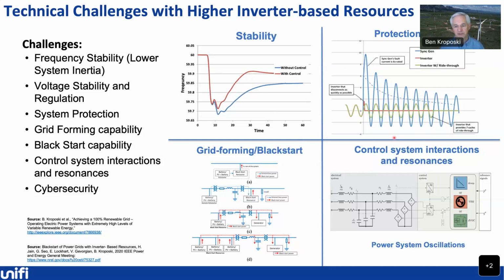There are still serious issues around protection systems and how to deal with the fact that you are eliminating large short circuit currents, which your protection system in your grid may be made of. There are lots of opportunities, whether you're looking at things like adding synchronous condensers into your system to provide that fault current if you want to maintain the existing protection system, or looking at having inverters provide slightly more than rated level current.